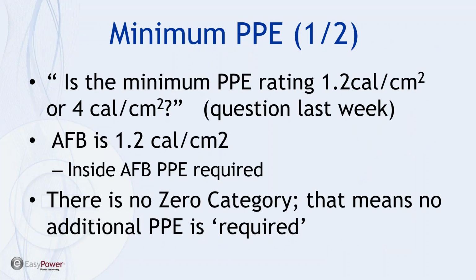Now, another question came up: is the minimum PPE rating 1.2 calories per square centimeter or 4 calories per square centimeter? Well, the question is a little bit misguided. The arc flash boundary is at 1.2 calories per square centimeter, so that's where the system requires PPE inside of that distance. There is no zero category, which means that below 1.2 calories, additional PPE is not required. But again, this will depend upon company policy, and it requires additional information or discussion about what that means.